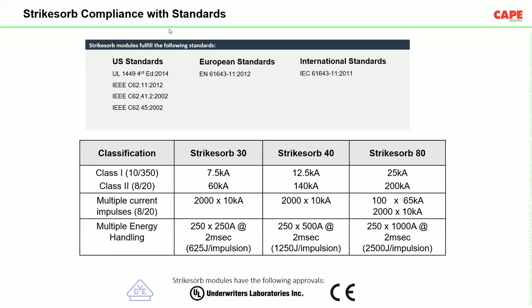See, the lightning also consists of a long duration stroke. So there are positive strike, negative strike, subsequent strike, and a long duration stroke. A long duration stroke is a small current but flowing for a longer duration. These SPDs are also tested for that particular purpose. You can see the strikes are 250 shots, 250 amps, 2 millisecond. 250 times these SPDs are tested.